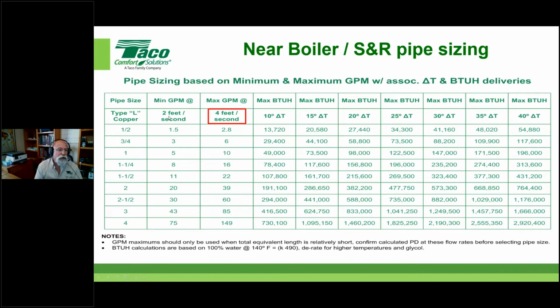And that's all this slide does. It just reminds you, if we stay between 2 feet and 4 feet per second, we're in the sweet spot, folks. You'll stay out of trouble. Again, it's got to apply to the pipe and type that you're using, but it keeps you out of trouble. And this is just showing you at a given delta T, what could you transfer at this maximum. For instance, if I had a 1-inch pipe and I ran 10 gallons a minute through it at a 20-degree delta T, what should that be? Right around 100,000 BTUs, and it is. But let's say that we went out to a 40 on a condensing boiler.